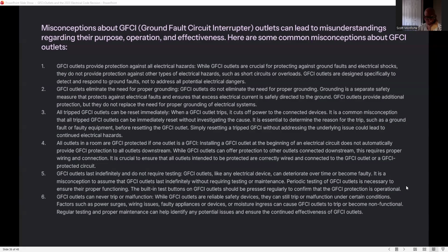GFCI outlets, like many electrical devices, can deteriorate over time and become faulty. It is a misconception to assume that the outlet will last indefinitely without requiring testing or maintenance. Periodic testing of a GFCI outlet is necessary to ensure proper functioning. The built-in test buttons on a GFCI should be pressed regularly to confirm that GFCI protection is operational.